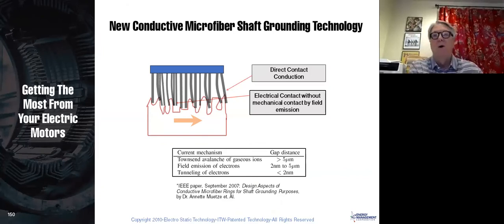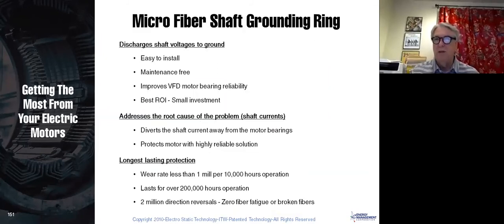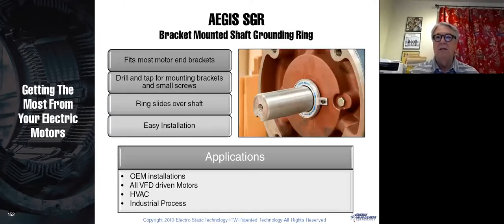There's another way to go, and that is by using what we call shaft grounding rings. These are the little carbon fibers that you see on your printer that take the static electricity off of there. I'm going to go to pictures because I think they make more sense. Here's a shaft grounding ring, and you can see the outside of the ring is attached to the motor frame. And then there are little tiny carbon fibers in here that actually touch the motor shaft, and they basically just short the shaft to the frame.